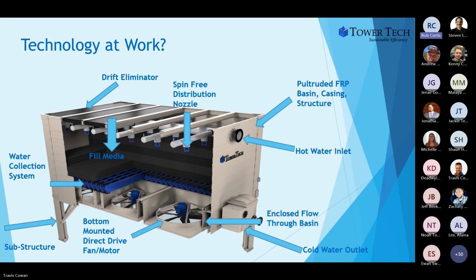And then the third feature of that is it is a multiple fan system. So we use what's called fan array technology. Actually, TowerTech originated that technology in 1990, 91. And we gained a reputation for that design concept in a cooling tower. And I guess it was received so well that the air side began developing that after us. And obviously, it's gained a very strong reputation as fan wall or fan array technology on the air side. But we actually originated that ourselves in the cooling towers years ago.